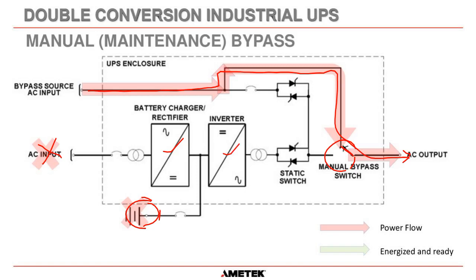But you have to understand that with a manual bypass switch mounted on the UPS itself, you will always have power on the terminals that connect the bypass inside the UPS enclosure. You will always have power on the output terminals inside the UPS. And you will also have power on the manual bypass switch contacts inside the UPS.